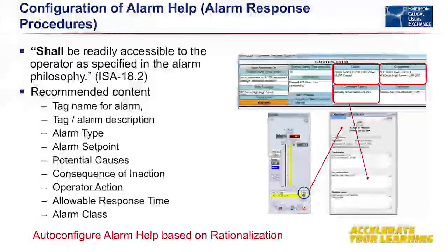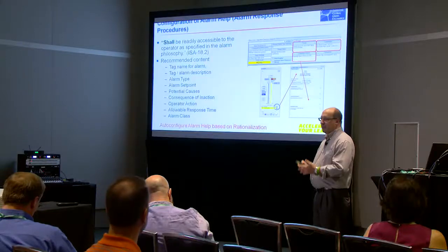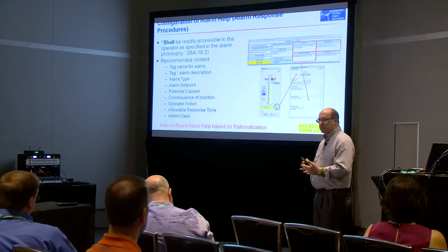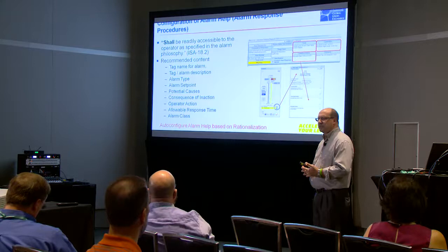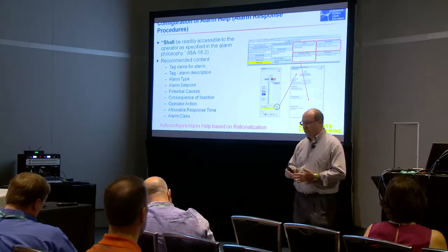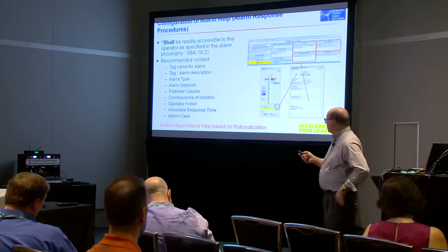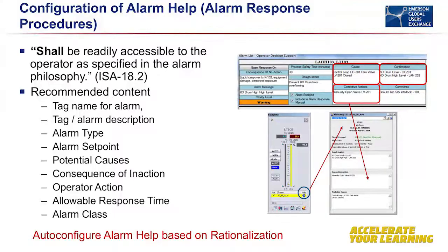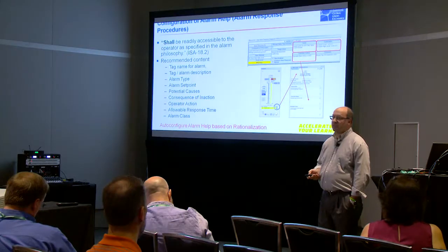Now, as part of the rationalization process, hopefully you're taking some of your most experienced operators. They're helping you determine what's the cause, what's the consequence, the corrective action. So this is also a knowledge capture process for your whole process facility. If you do this and you capture the information in the SILAlarm tool, then we can push that into DeltaV and populate the alarm help faceplate.